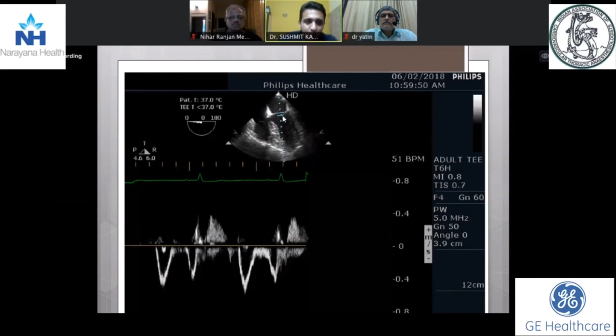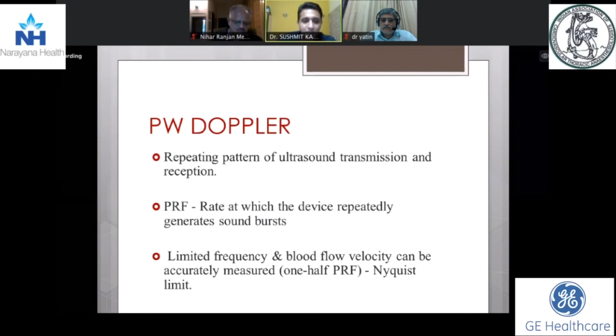Hence, only a limited frequency and blood flow velocity can be accurately measured by pulsed wave Doppler, which is one half of the pulse repetition frequency, known as the Nyquist limit. So as long as we are interrogating a velocity within the Nyquist limit, it will accurately show the direction and the velocity. But if you are interrogating a velocity higher than the Nyquist limit, the signal will get ambiguous, which is known as aliasing, wherein the velocity cannot be determined and the direction may be shown as opposite. In spectral display, this may also be seen as a wraparound.